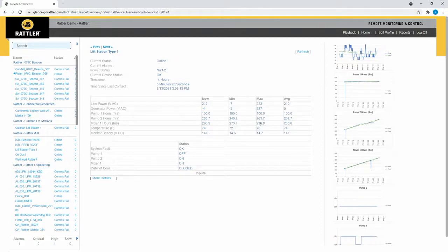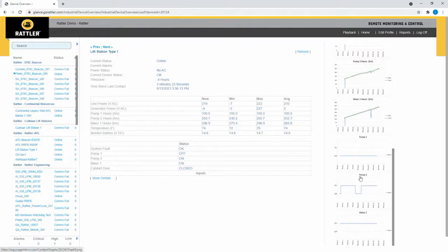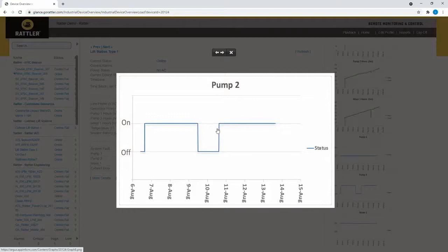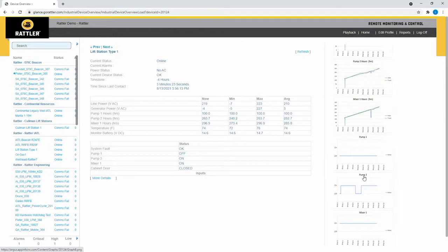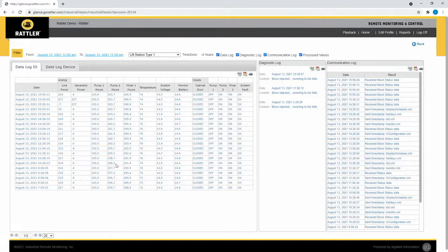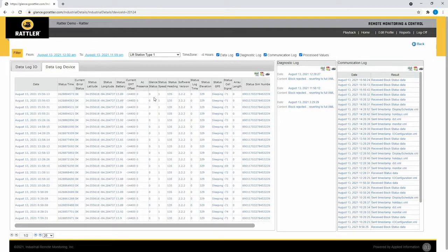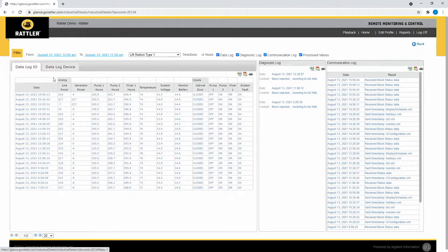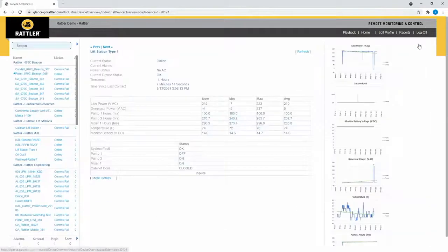Again, this is quite useful information which can be produced into all sorts of usable reports, including the utilization of when the pump was on and off and so forth. This allows for some really effective reports to be written and viewed. What you do see is more details. This is the detailed raw information that's come back from the device, including its GPS coordinates and all kinds of things, the SIM card number. This is for remote diagnostics, not required by the user, because the information they need is all on what we call level 1 and level 2.